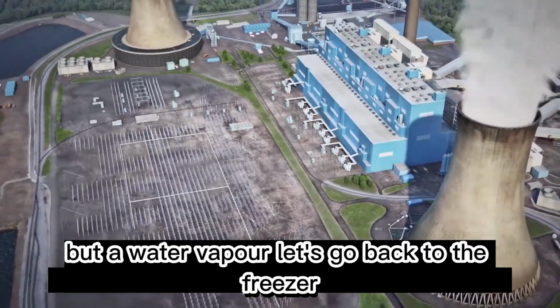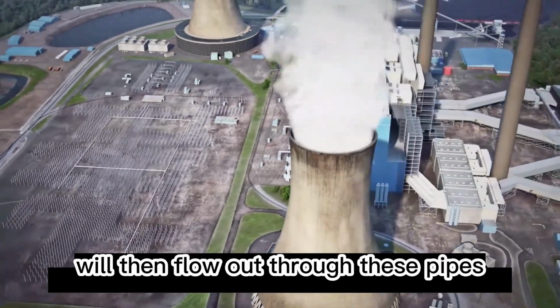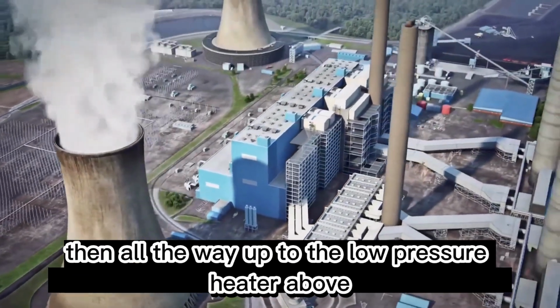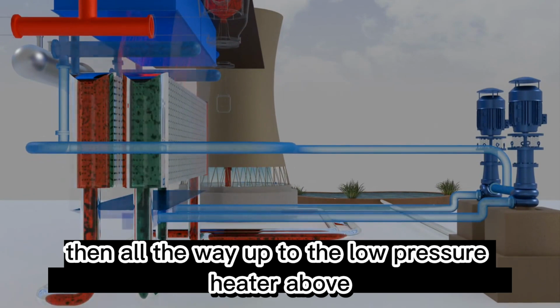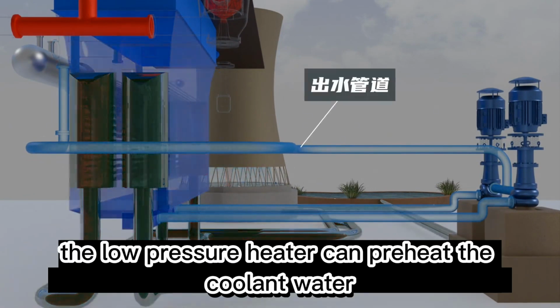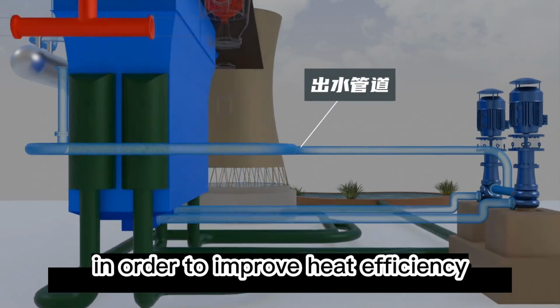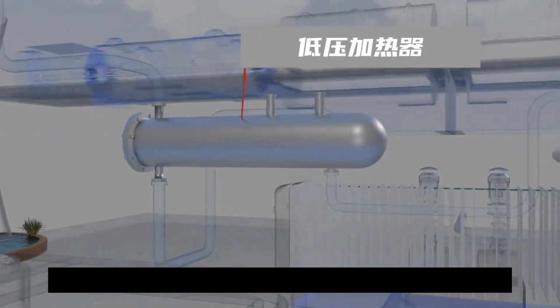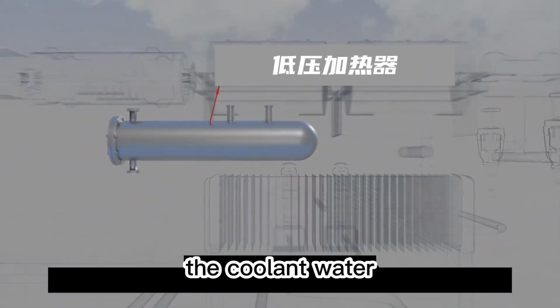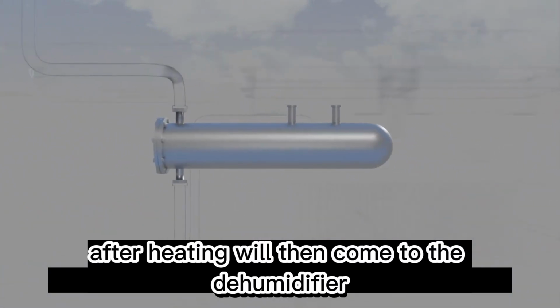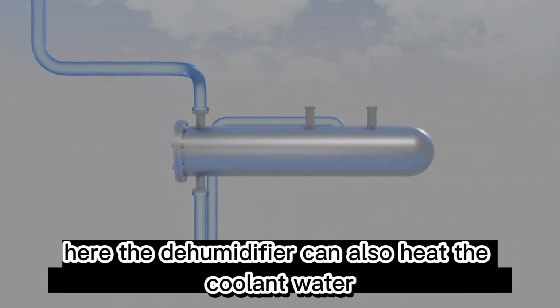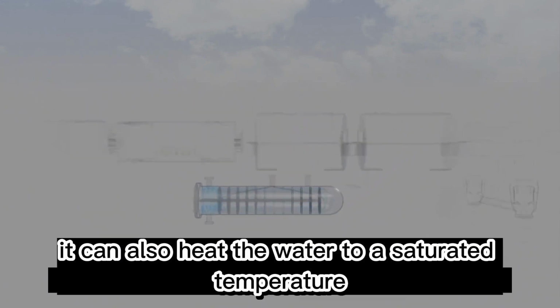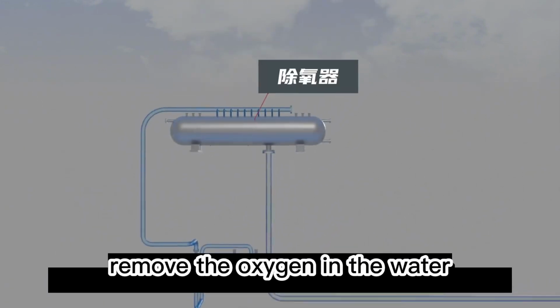The frozen water from the freezer will then flow out through these pipes, then all the way up to the low-pressure heater above. The low-pressure heater can preheat the coolant water in order to improve heat efficiency. At the same time, it can prevent the coolant water from entering the boiler directly, causing the boiler equipment to be damaged. The coolant water after heating will then come to the deaerator here. The deaerator can also heat the coolant water. At the same time, it can also heat the water to a saturated temperature. Remove the oxygen in the water and other gases in order to prevent the equipment from corrosion.